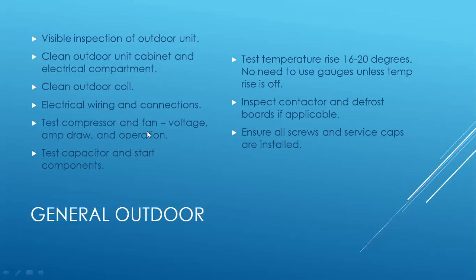Always check your compressor and your fan. You want to check your incoming voltage. You definitely want to check your amp draw, compare that to the data plate, and then check the operation. Now that's kind of a listen and look type of deal. So if it sounds good, you're probably okay. But look at your voltage, amp draw, and operation. Always test capacitors and any kind of start components that you have. Those will come back to bite you.